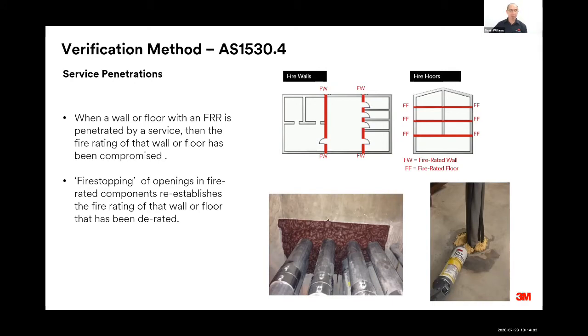And so a method of restoring that fire resistance rating is required. And for pipes and cables, we've seen presentations on fire stopping previously through the TechEd webinars. And again, in this case, it can involve different fire stopping materials to reinstate that fire resistance rating of the wall or the floor through a combination of different materials that have all been tested in that configuration.